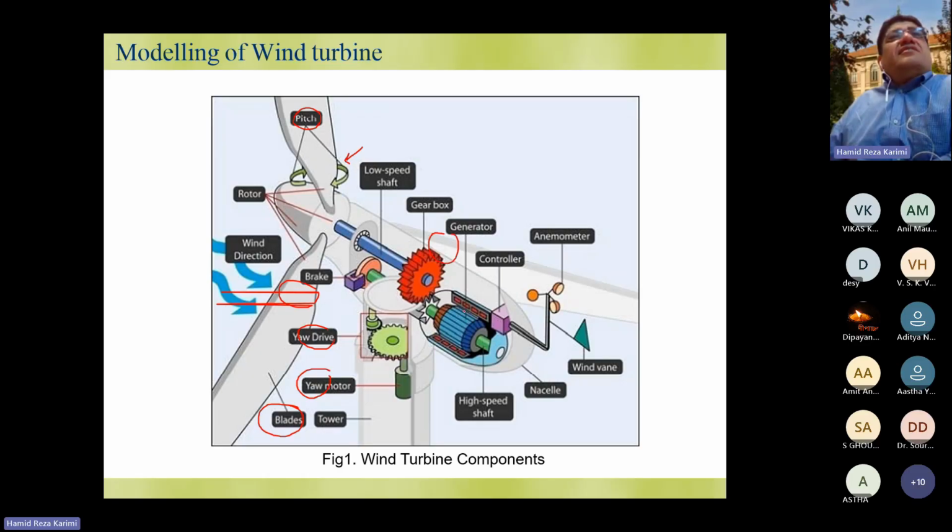And this is the nacelle. The nacelle has the gearbox and also the generator. And the nacelle has two shafts. One shaft is the lowest speed, up to the gearbox, and the second shaft is the highest speed because of the gearbox. So this side is the highest speed, the left is the lowest speed. And then you have a control from.